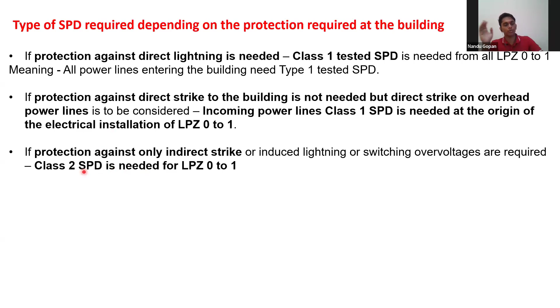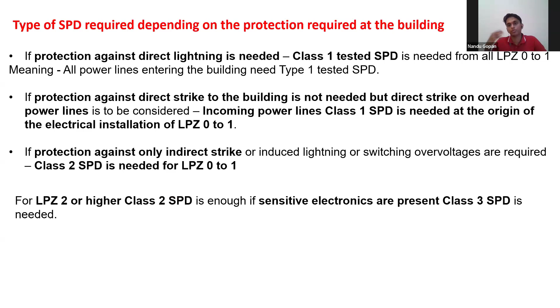So zone 0 to 1 is clear. If you want direct strike protection, you have to have class 1 SPD. If you care only about indirect strikes, then you go for type 2 SPD. Inside the building, you are supposed to go for type 2 SPD. You don't need type 1 SPD. If there is some sensitive equipment, then within 10 meters of the equipment you can have a class 3 SPD. That will give much more reliability for the equipment.